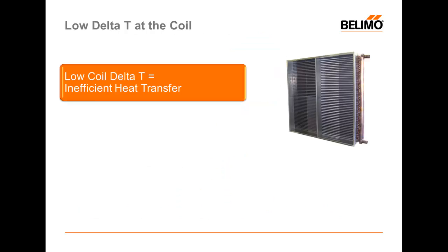Let's first talk a little bit about Delta-T. Delta-T at the coil refers to the difference between the supply and return water temperature from your coil. When you send very cold water down to your chilled water coil, if you do not transfer enough heat, that water will remain cold and get sent back to your chiller at a colder temperature than is designed. This is what's known as a low Delta-T.